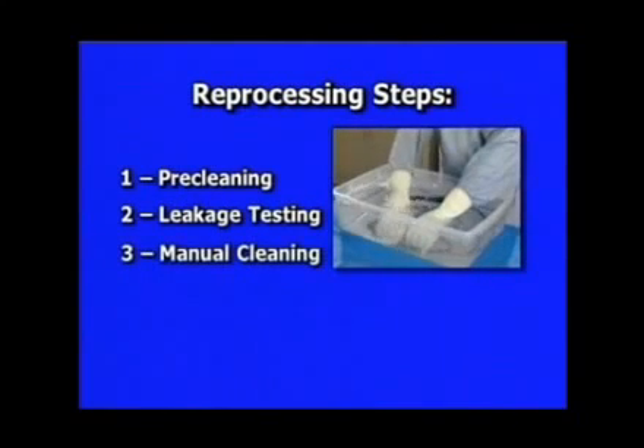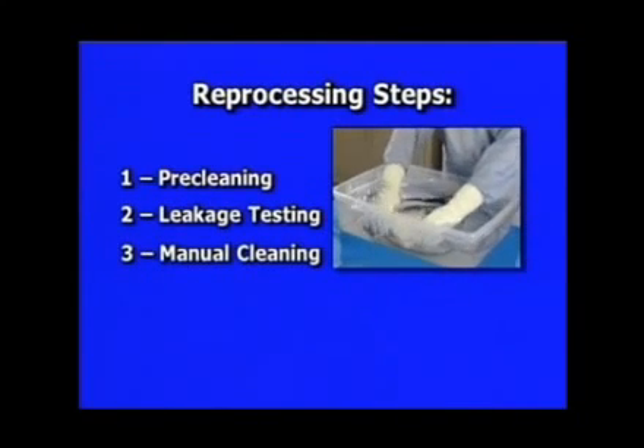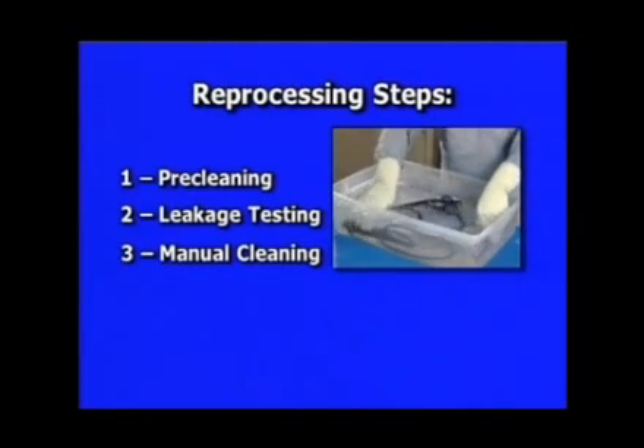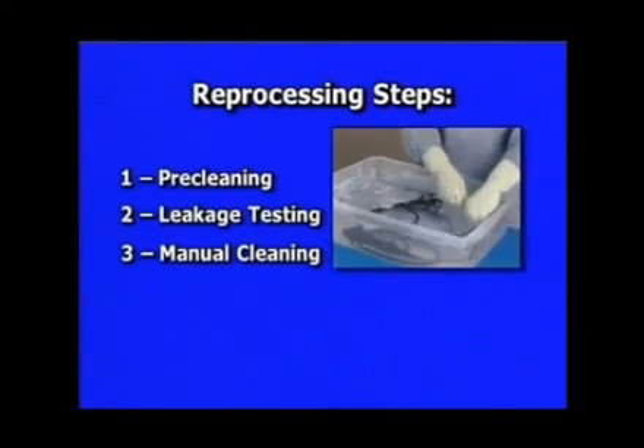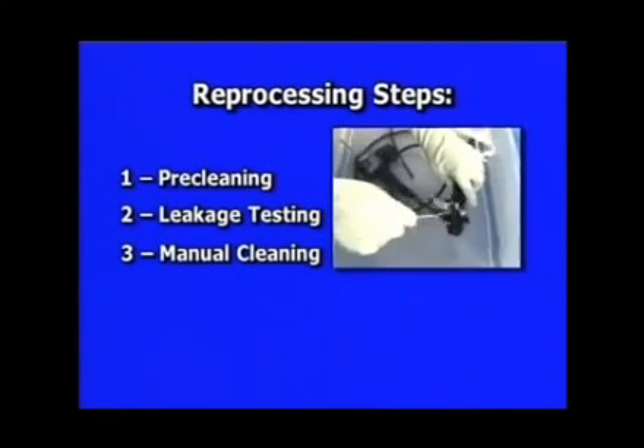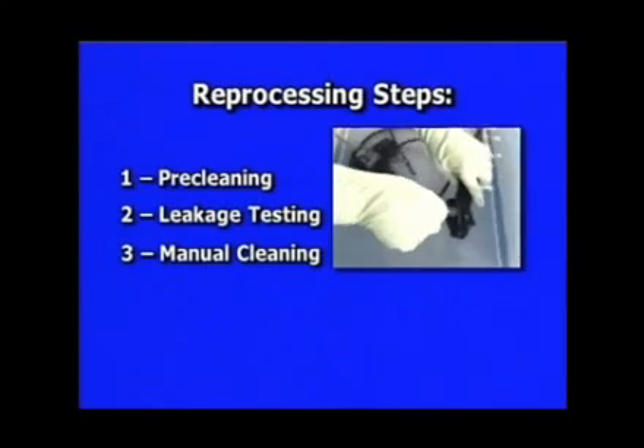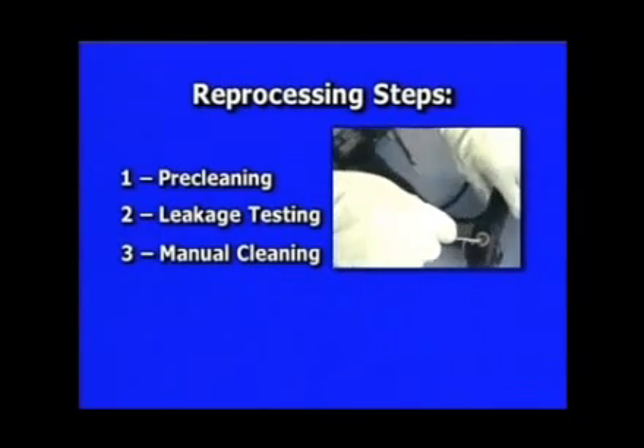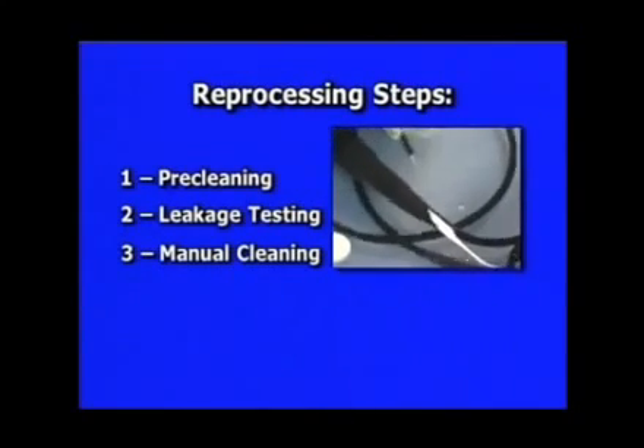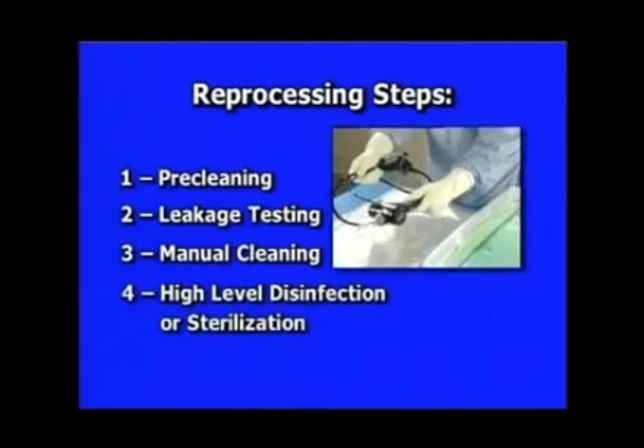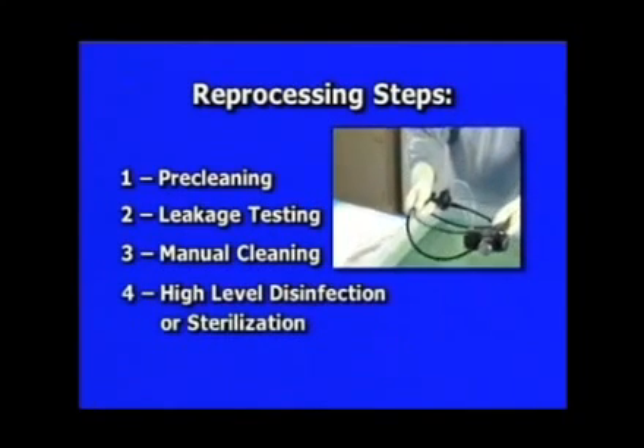3. A critical step is meticulous manual cleaning with a detergent or enzymatic solution. Use appropriate brushes and cloths to thoroughly clean all exterior surfaces and internal lumens. High-level disinfection or sterilization is the next step.